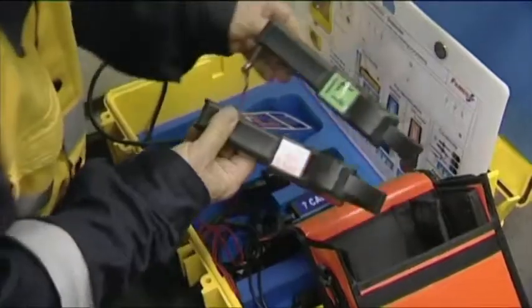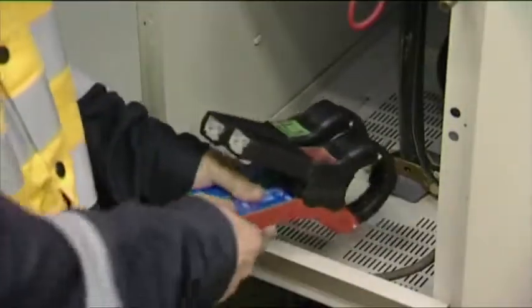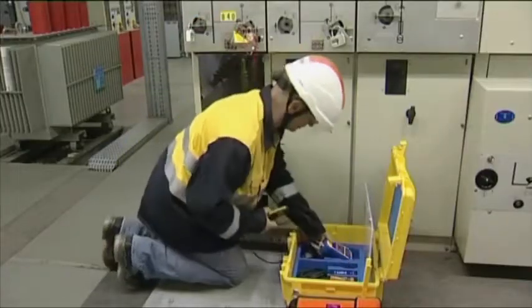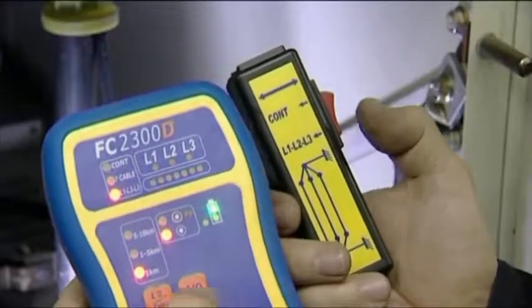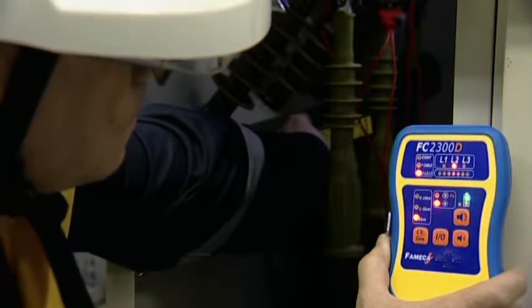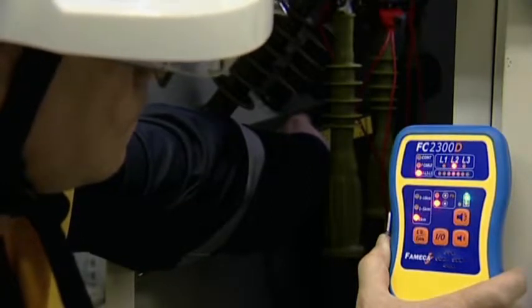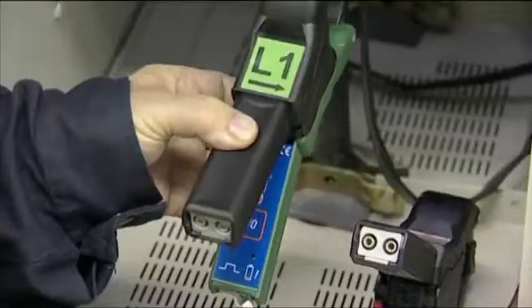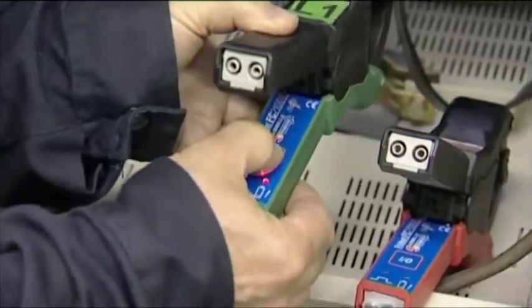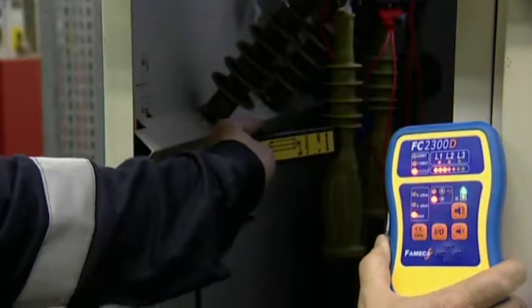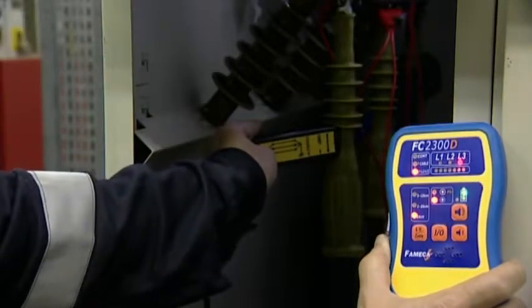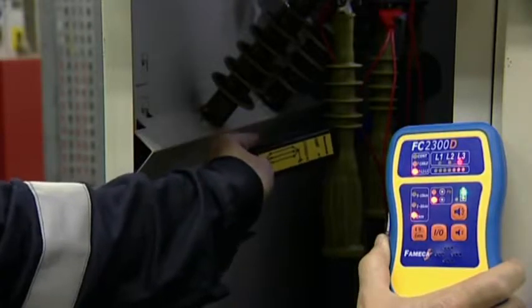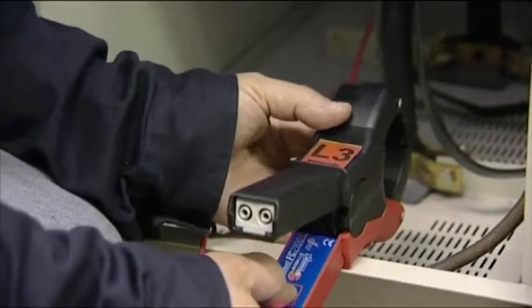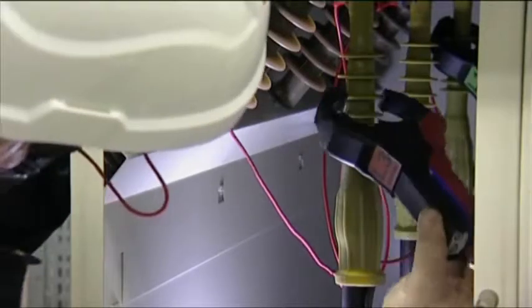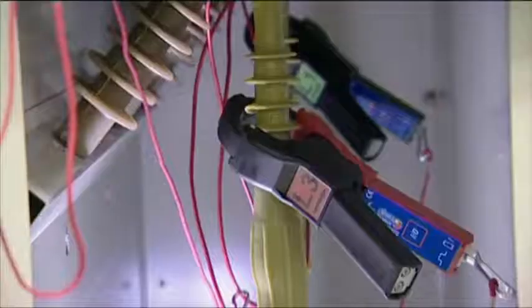FC2300 cable identification. Still on Substation 1, you can now test the phases, again using the FC2300 by Fameca, and we point out with no additional maneuver required. We can now install the two individual transmission clamps of the FC2300 on phases 1 and 3. Thanks to these two clamps, we will be able to identify conductors on the cross-section of this cable at the work site.